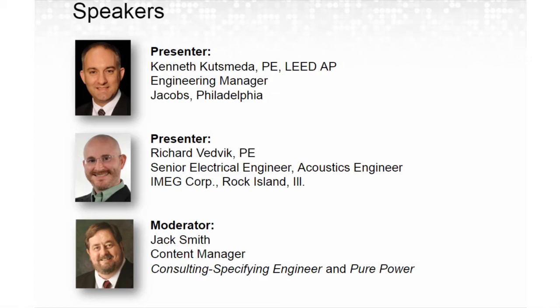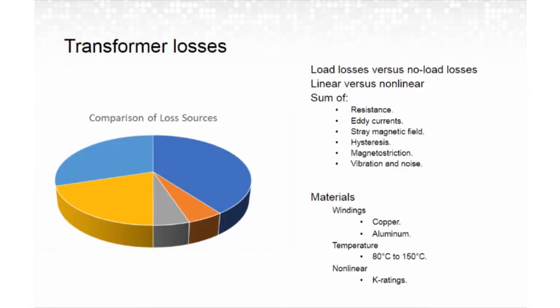Thanks, Jack. So when we were in the slide with the unlabeled pie chart, listing all of the different losses that transformers can have, both eddy currents and magnetostriction are responsible for the humming and the buzzing and the vibrations. When we think about magnetostriction, essentially the flux in the core is causing the core itself to physically expand and then contract slightly as the alternating magnetic field affects the core. So you can imagine that expansion and contraction is essentially what would cause those friction losses as well as that vibration. Thanks, Jack, for bringing that slide up.